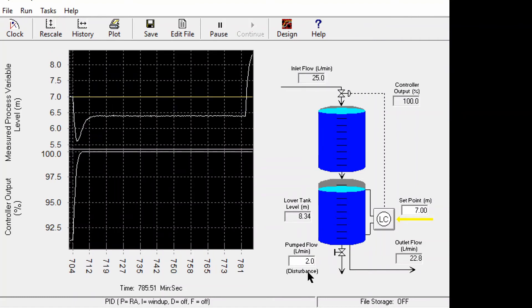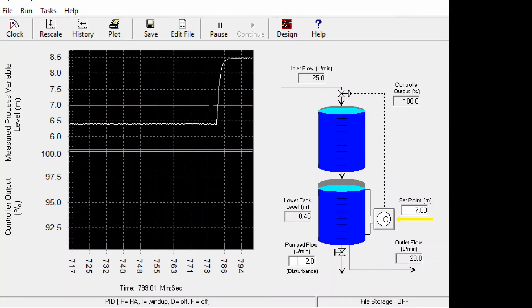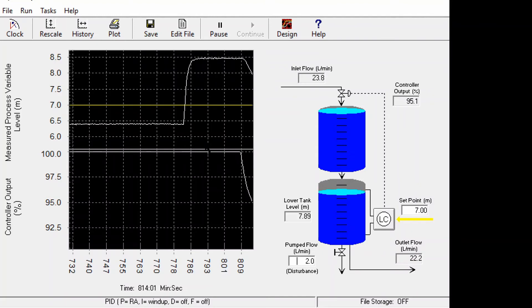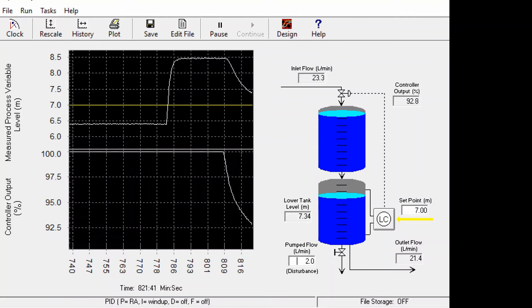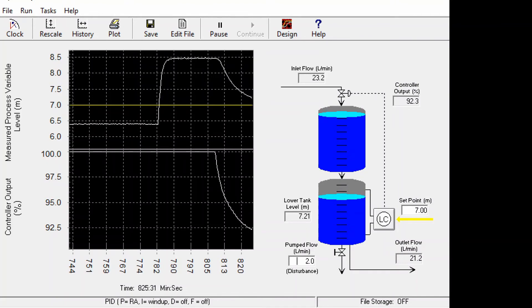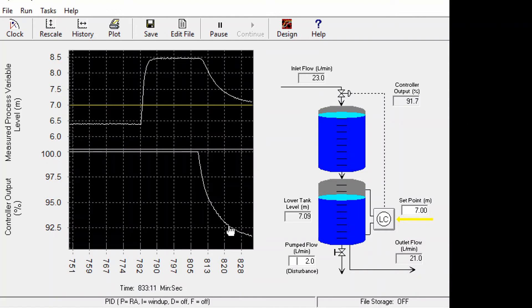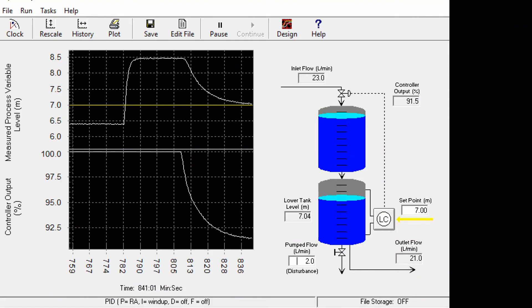Now the disturbance changes back to 2. However, the controller remains at 100% and the output goes beyond the set point value. The controller does nothing because due to the integral action the calculated value is more than 100%. It takes this extended time to come back below 100%, and only then does the controller take action and bring the process to the desired value.